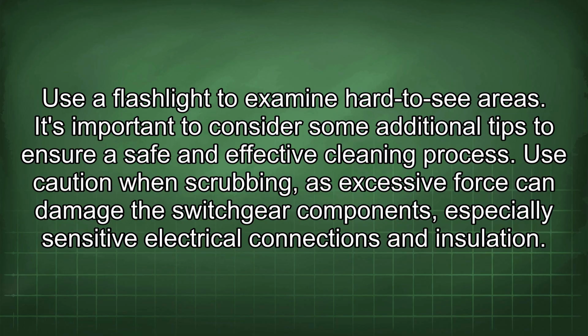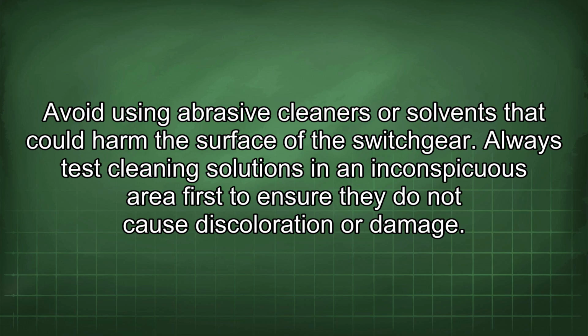It's important to consider some additional tips to ensure a safe and effective cleaning process. Use caution when scrubbing, as excessive force can damage the switchgear components, especially sensitive electrical connections and insulation. Avoid using abrasive cleaners or solvents that could harm the surface of the switchgear. Always test cleaning solutions in an inconspicuous area first to ensure they do not cause discoloration or damage.